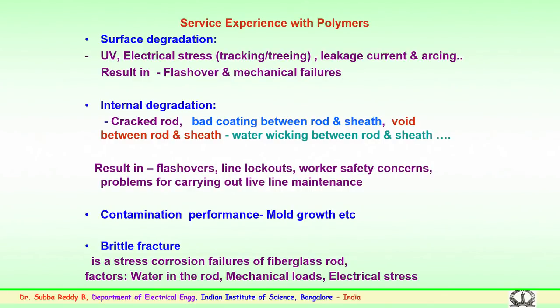It could also be because of the UV radiation from corona discharges at the corona control rings, which are fixed on either side of the metallic fittings near the insulators. If the corona control rings are not properly placed or not properly designed, corona discharges continuously hitting the insulator surface over a period of time could damage it. Because of moisture, pollution, fog or snow entering the damaged surface, nitric acid could form. Here again, failures have been reported over a period of time.